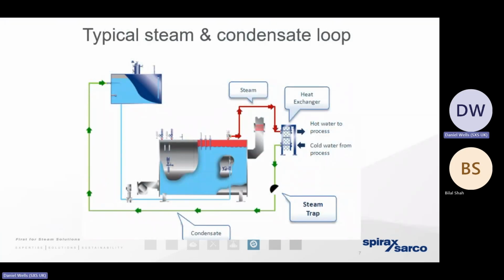Loop. We always refer to a steam system as being a loop. In a typical or a traditional steam system, we could have 1 or more, anywhere up to 6 horizontal fire tube steam boilers. Spirax Sarco don't manufacture steam boilers, but we do manufacture the vast majority of the controls that sit around the boiler house to ensure that the best condition of steam is generated at the best possible quality and condition, as efficiently as we can. We don't want to burn too much gas, but most importantly of all, to ensure that that boiler is operating safely.